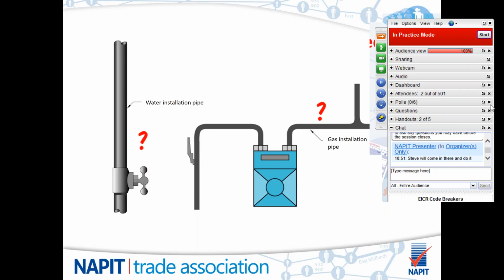metallic water installation and gas installation pipes within the property. As it stands, touching those pipes will not hurt. If a fault develops and those pipes do become live without proper earthing, the protective bonding conductors in place, and the operation, of course, of the protective device, these pipes could remain live and somebody could get seriously injured off them.